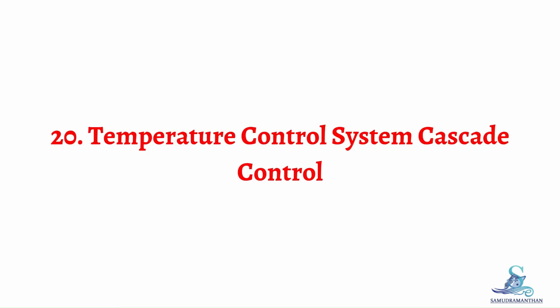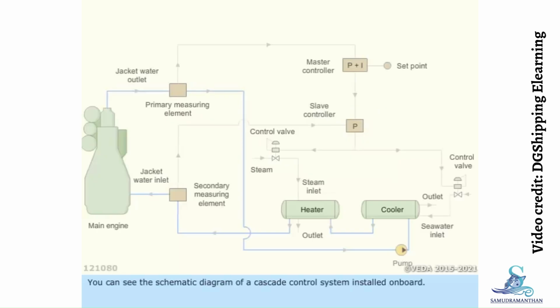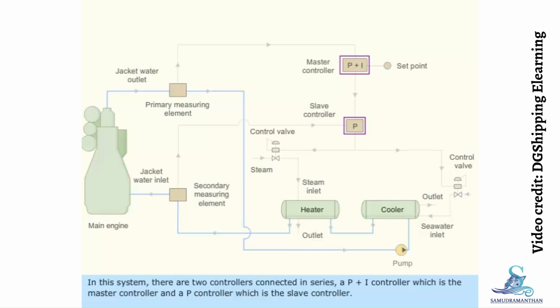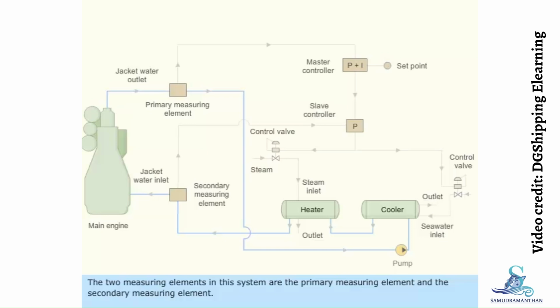Topic 20: Temperature Control System Cascade Control. You can see the schematic diagram of a Cascade control system installed on board. In this system, there are two controllers connected in series, a P plus I controller, which is the master controller, and a P controller, which is the slave controller. The two measuring elements in this system are the primary measuring element and the secondary measuring element.